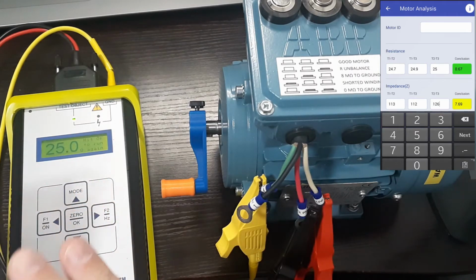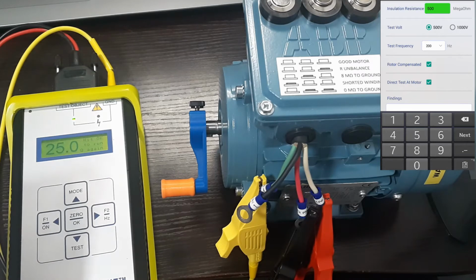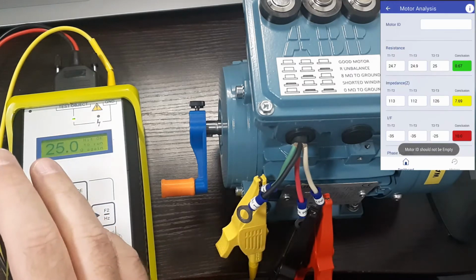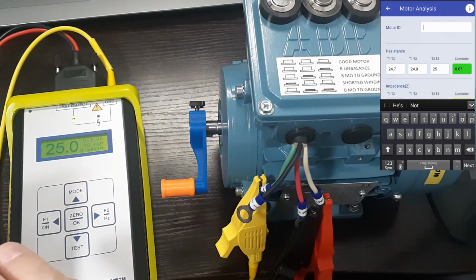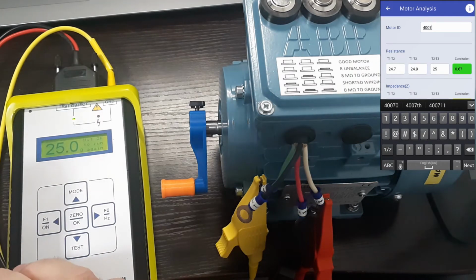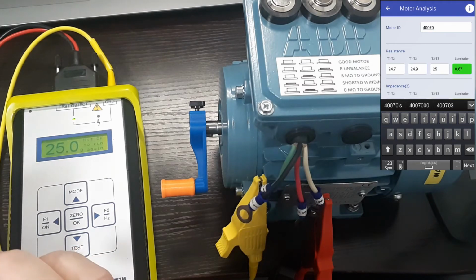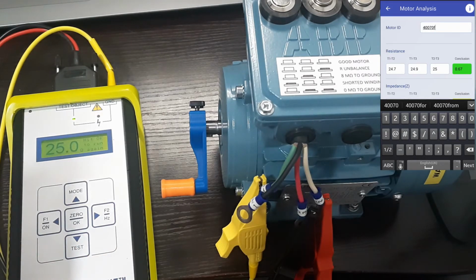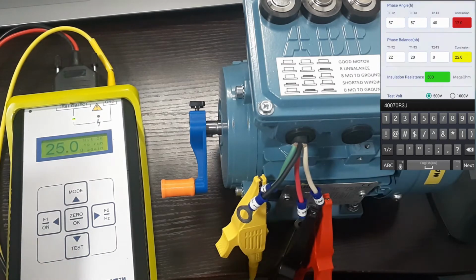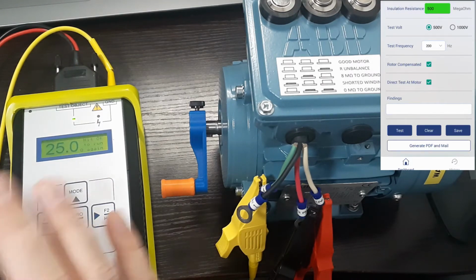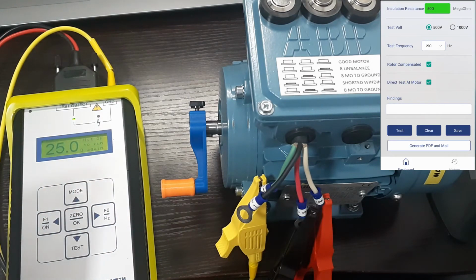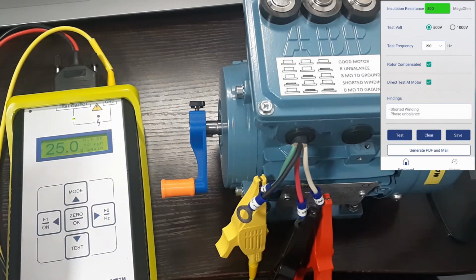Well, I'm going to go down here. We're going to press the test button. Oh, motor ID. Okay, so I'm going to put in the motor part number here. And I'm labeling this separately as F3. So this is the shorted winding. So test. Shorted winding, phase unbalance. And that's exactly what we should be testing for here.